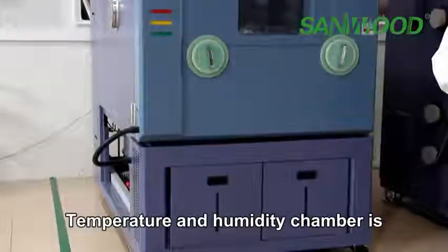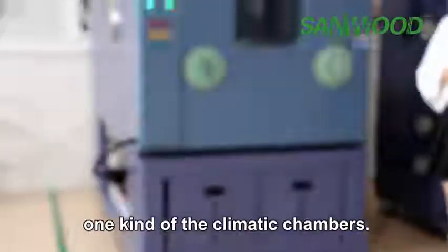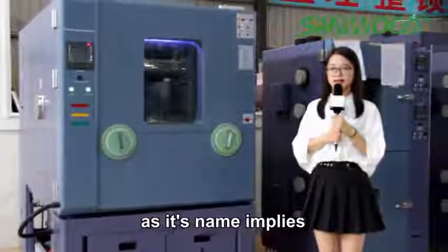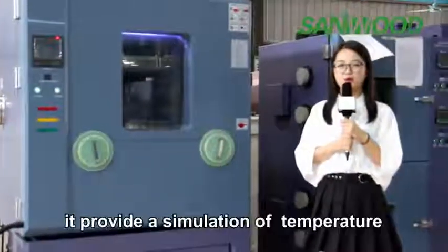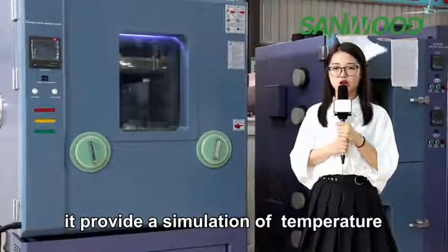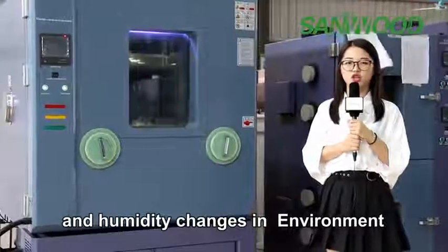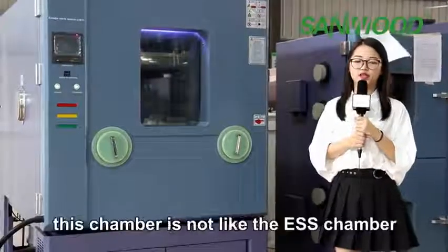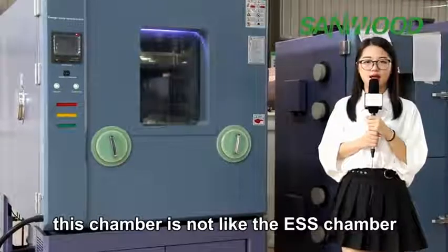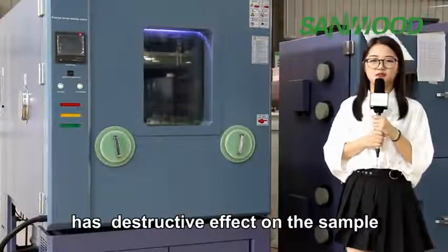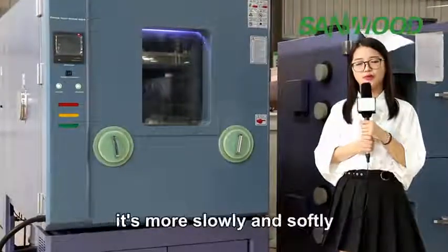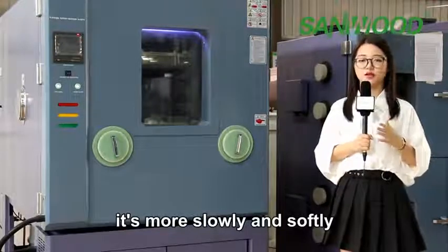Temperature and humidity chambers are one kind of climate chamber. As its name implies, it provides a simulation of temperature and humidity change in the environment. This chamber is not like the ESS chamber, which has a destructive effect on the sample. It's slower and softer.